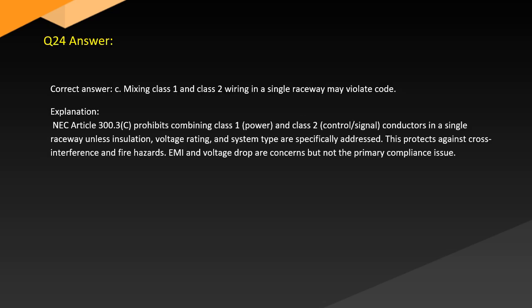Answer. Correct answer: C. Mixing Class 1 and Class 2 wiring in a single raceway may violate code. Explanation. NEC Article 300.3(C) prohibits combining Class 1 power and Class 2 control signal conductors in a single raceway unless insulation, voltage rating, and system type are specifically addressed. This protects against cross-interference and fire hazards. EMI and voltage drop are concerns but not the primary compliance issue.